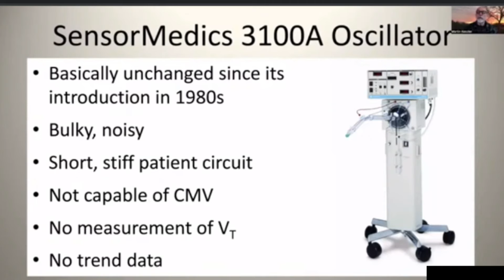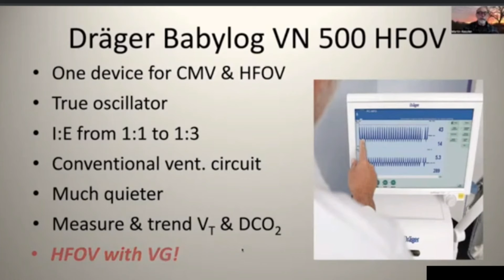So the Babylog VN500 and its newer iterations, of course, can do both high frequency and conventional. It's a real oscillator. It gives you perfect sinusoidal waveform at 1:1 ratio. It can go from 1:1 to 1:3. It uses this low compliance conventional ventilator circuit. It's much quieter than the SensorMedics. And it, of course, measures tidal volume and a measure of CO2 elimination. And what really turns me on is it can do volume guarantee.